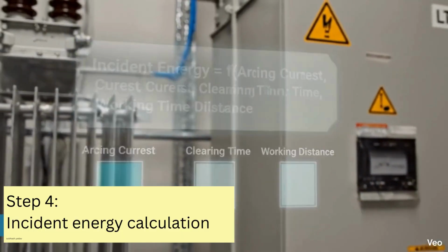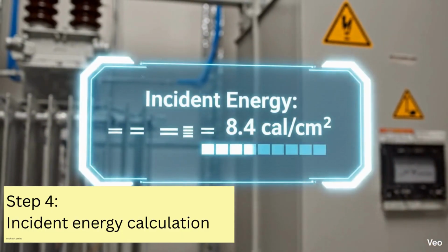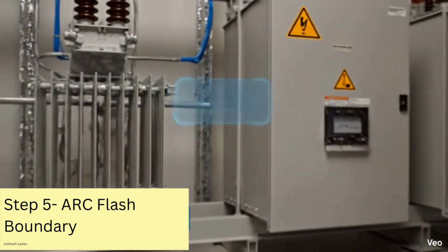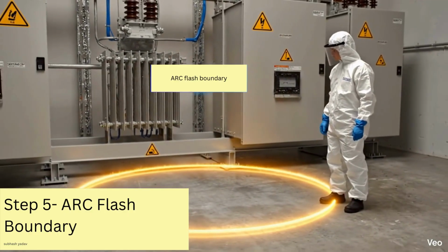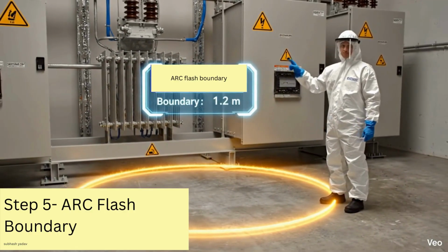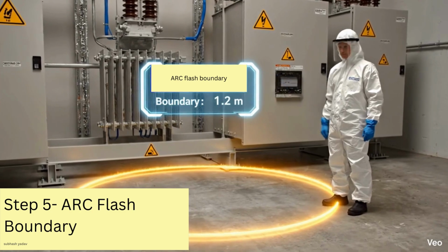Using arcing current and breaker clearing time, the software calculates the incident energy at the working distance. Arc flash boundary is set to show how far energy can cause injury. Workers must stay outside this limit.